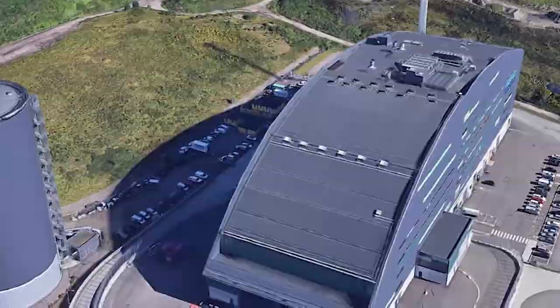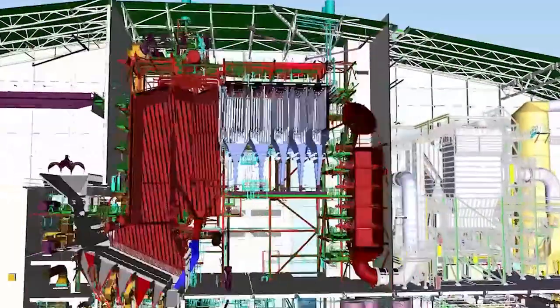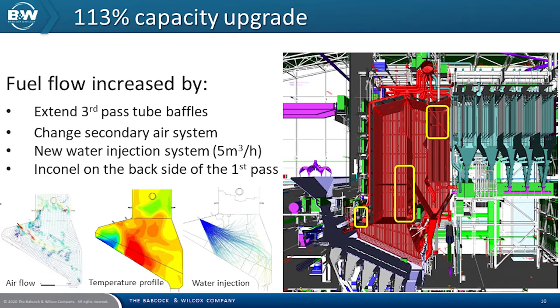Let's have a look at the plant itself in more detail and go through where the upgrades were made. The illustration shows the main areas that we had a look at. We were able to increase the capacity and the fuel flow by extending the third-pass tube baffles. We changed the secondary air system, installed a new water injection system, and applied Inconel on the backside of the first pass. We were able to increase the fuel input up to 113%.